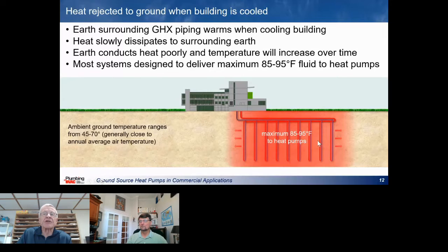If it's a cooler temperature that you're working with, the heat pump is going to work more efficiently. So you're starting with a ground temperature in Canada about 45 to 55 degrees. You're going to warm up the dirt around the pipe up to about 85 or 95 degrees by the end of summer.